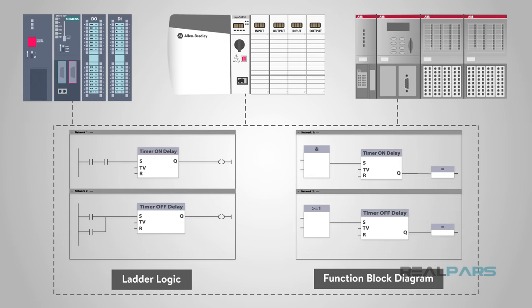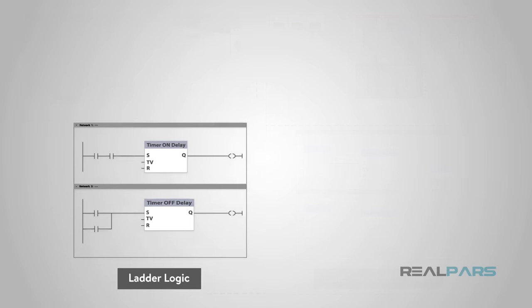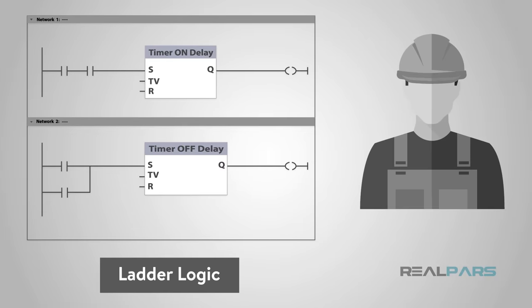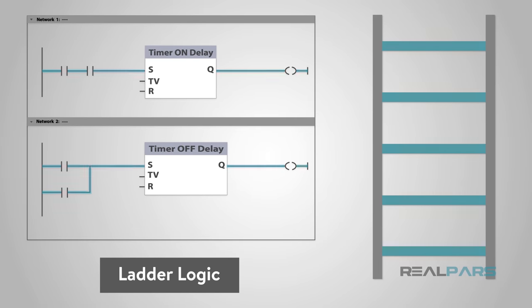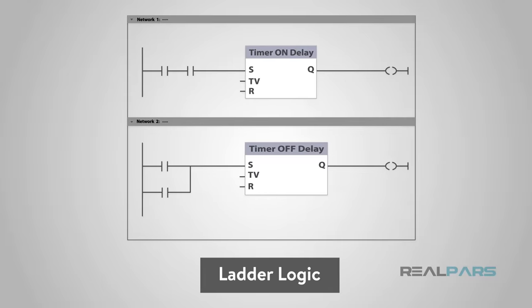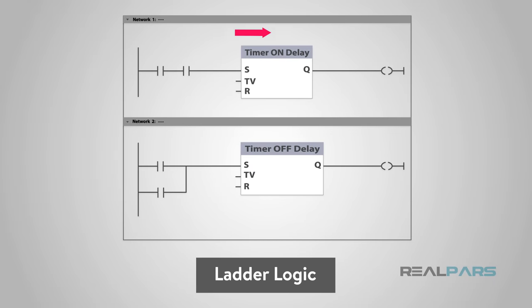Ladder logic is pretty well the universal programming language of PLCs. It has been around for decades and is pretty well understood by most technicians and engineers alike. It is named ladder logic because it quite literally looks like a ladder. The vertical lines are referred to as the power rails. The horizontal lines that our programming bits are located on are rungs, just like on a ladder. It is read from top to bottom and left to right.